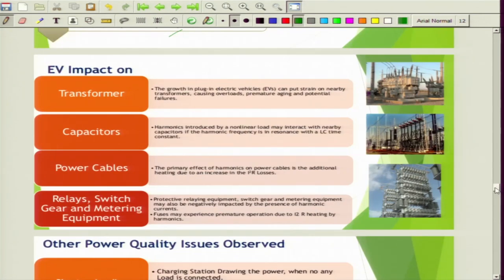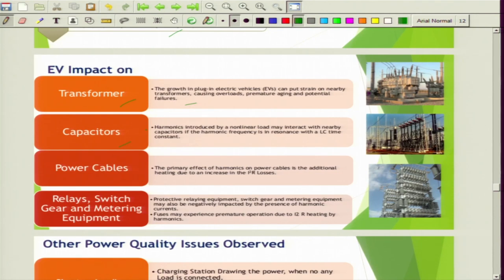In summary, the growing number of electric vehicles can put strain on transformers, causing overloads, premature aging, and potential failures. The system will have shunt capacitors placed for power factor correction or reactive power injection. Harmonics introduced by non-linear loads may interact with nearby capacitors if the harmonic frequency is in resonance with the LC time constant, which may hamper system stability. The primary effect of harmonics on power cables is increased losses.